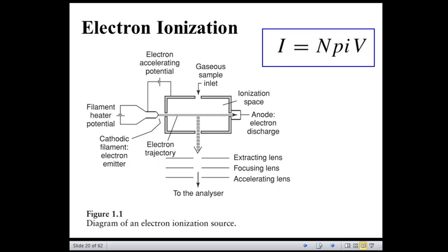This ionization technique works very well for gas phase molecules. So what you can expect? Extensive fragmentation, so that the molecular ions are not always observed. That is the reason why this particular electron ionization method is not used for most biological samples, because it works very well for many gas phase molecules, but it induces extensive fragmentation.